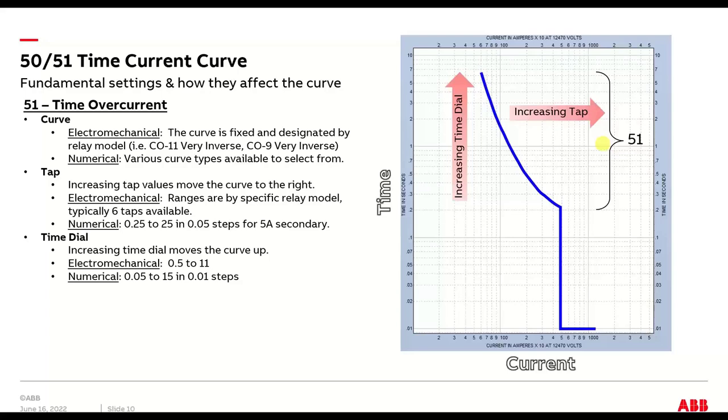And generally, say, for example, that you wanted protection for 200 amps worth of cable. You would set your tap pickup on this 51 device to pick up at 200 amps. So that basically this level here, somewhere around here, at almost infinite time, would be about 200 amps. But then you see as the time gets smaller and smaller, that 200 becomes like two per unit, 400, 600, whatnot. So that's the function of the 51 device.